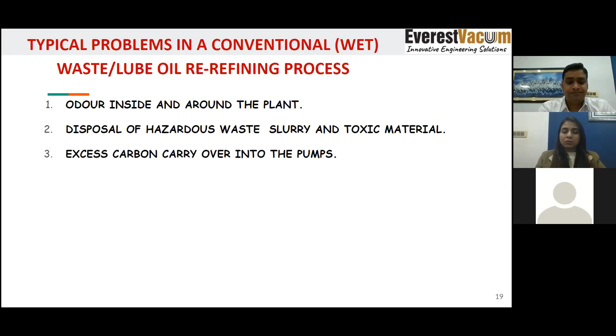Excess carbon carryover into the pumps is quite related to the second point. Since we are operating in the high vacuum and low temperature ranges, the carbon cracking is not happening. So we save on carbon carryover, which enhances the life of the machines performing the vacuum generation.